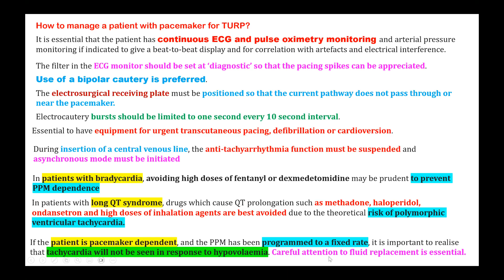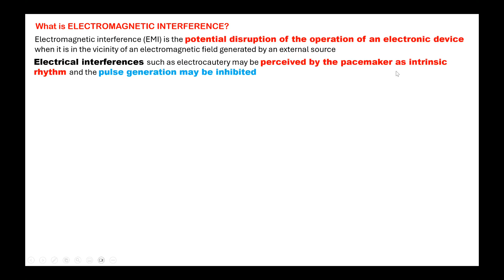Then coming to the most important complication which can affect the functioning of a pacemaker or AICD is the electromagnetic interference. What is electromagnetic interference? Do you know the answer? Right. It's a potential disruption of the operation of a pacemaker which is in the vicinity of an electromagnetic field generated by an external source. And interference can be due to the electrocautery being perceived by the pacemaker as an intrinsic rhythm of the heart. So any electrical current passing from the electrocautery, the pacemaker will identify as though it is a conduction or a current from the cardiac contraction, and pulse generation may be inhibited. So it will try to reduce the rate that is applied by the pacemaker. That will lead the patient to bradycardia.